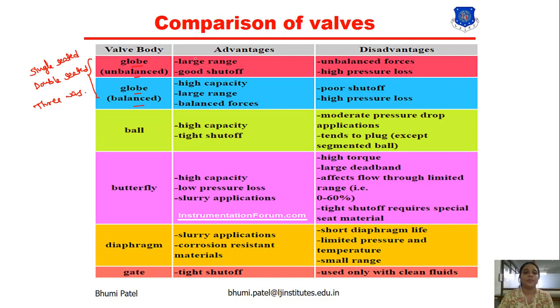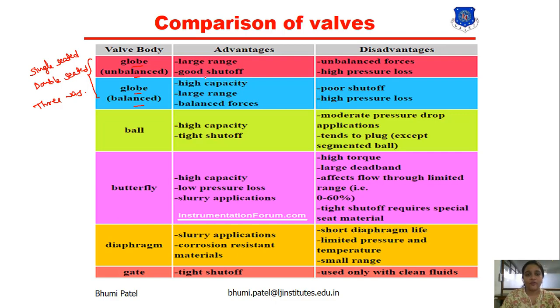In the unbalanced globe valve, the shutoff ratio is good because in the single seated and double seated configurations, we use a plug in the system, giving good shutoff performance. The disadvantage is we can get unbalanced force and high pressure loss, because the plug is connected with the valve body and if not properly connected, we get a pressure loss.